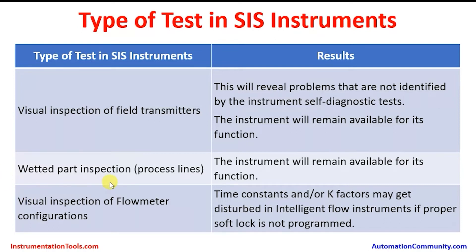Wetted part inspection: this is for the process lines, and the instrument will remain available for its function. Visual inspection of flow meter configurations: time constants and K-factors may get disturbed in intelligent flow instruments if a proper soft lock is not programmed. Soft lock means there is an internal lock requiring an enabling key — like password protection. This is applicable for inline flow meters of later technology, such as Coriolis mass flow meters, vortex flow meters, and magnetic flow meters.